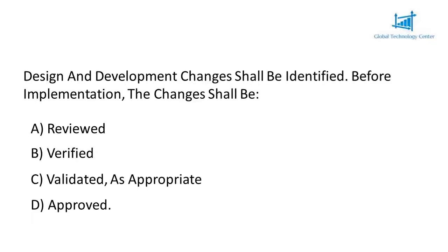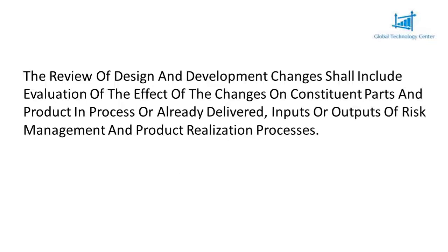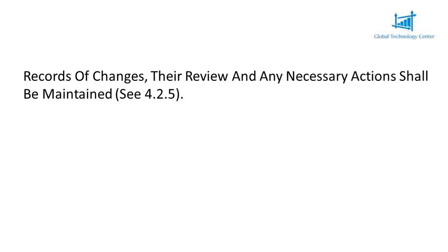The review of design changes shall include evaluation of the effect of the changes on constituent parts and product in process or already delivered, inputs or outputs of risk management and product realization processes. Records of changes, their review and any necessary actions shall be maintained.